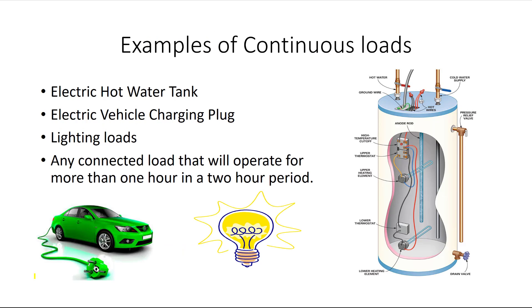Now let's look at some examples of continuous loads. An electric hot water tank can easily operate for more than one hour in a two-hour period. If there is a constant demand for hot water within a building, the electric hot water tank will continually be heating the water. Lighting loads within a house — we have all left the lights on for more than an hour, so that qualifies them as a continuous load. Our electric vehicles and the charging receptacles used to charge them are also considered continuous loads, because the batteries may take far longer than an hour to charge, keeping that receptacle under full load.